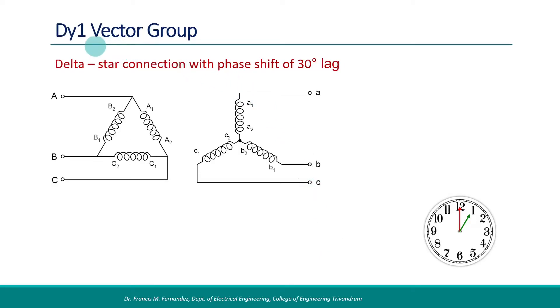Now the DY1 vector group — the primary is delta connected and the secondary winding is star connected. Since we have taken line voltage VAB as reference for the primary side, VAB should be considered for the secondary side also. In the star connected secondary, VAB is obtained by VA minus VB, and the VAB phasor is obtained accordingly. Here also the secondary voltage is lagging by 30 degrees from the primary side — the 1 o'clock position matches here as well. The simplified connection diagram and the displacement diagram clearly represent the delta-star connection and the 30-degree lagging phase angle.